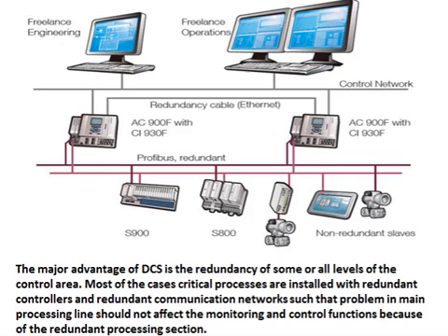The major advantage of DCS is the redundancy of some or all levels of the control area. In most cases, critical processes are installed with redundant controllers and redundant communication networks, such that a problem in the main processing line should not affect the monitoring and control functions because of the redundant processing section.